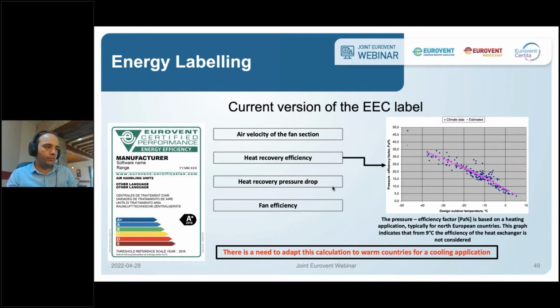And in this graph, for example, you could see that if you are at -10 degrees Celsius outdoor, it means that 1% more efficiency in your heat recovery system is equivalent to 15 Pascal less in your system. So this factor allows you to make the link between the heat recovery efficiency and, for example, the pressure drop of the components. In this way, you can compare all these parameters and have as a result the overall classification.